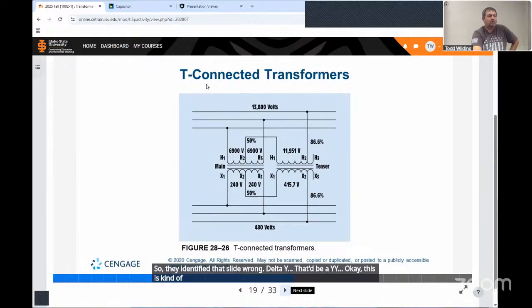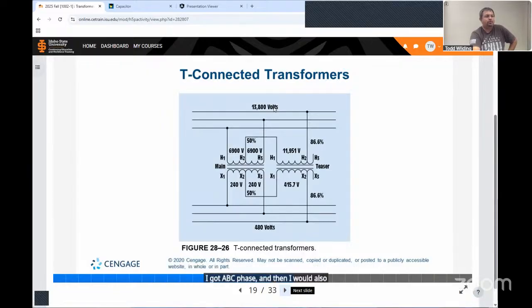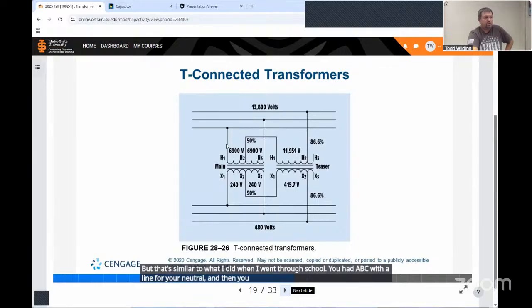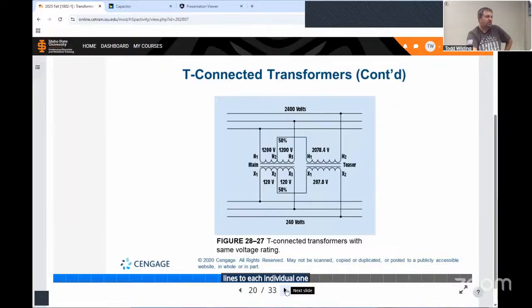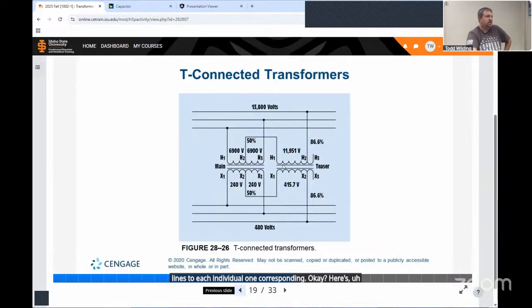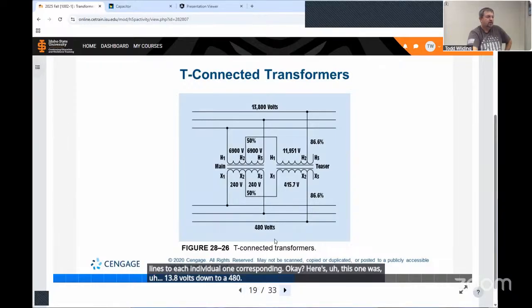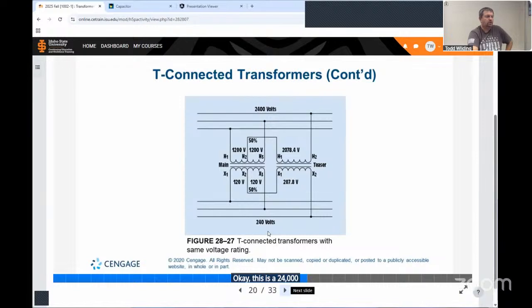This is kind of how I grew up, went through the program with the lines up here. I got A, B, C phase, and then I would also have a neutral line up there. The fourth one would say neutral. This is only a T connection with two transformers, but that's similar to what I did when I went through school. You had A, B, C with a line for your neutral, and then you would take your lines to each individual one corresponding. This one was 13.8 kilovolts down to a 480. This is a 2,400 volts down to 240 volt. Just showing you the T connected transformer with the same voltage rating, how to do those.